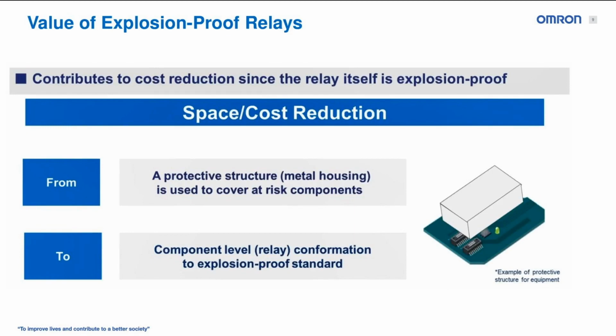Now, what is the value of explosion-proof relays for those of you using semi-flammable refrigerants or semi-flammable gases in general in your applications? Well, it contributes to cost reduction since that relay itself is an explosion-proof product. It is no longer an ignition source. It is a space and cost reduction. If you look at the box here, we typically would have to protect, using a metal or other type of housing, all of the elements that are at risk for ignition in an application with a flammable gas. Or you would have to have some isolation between the switching or ignition components and the product itself.